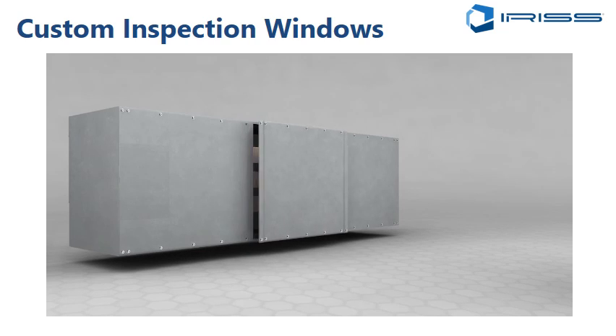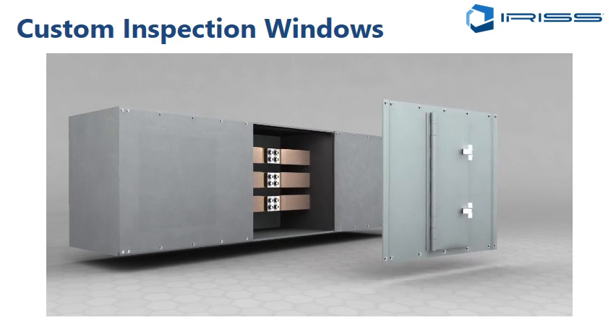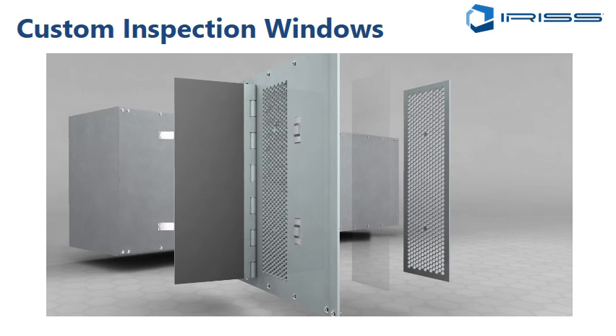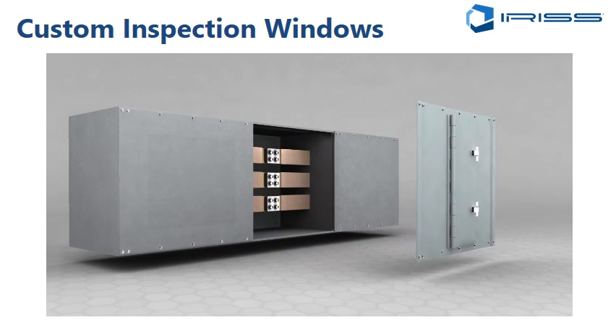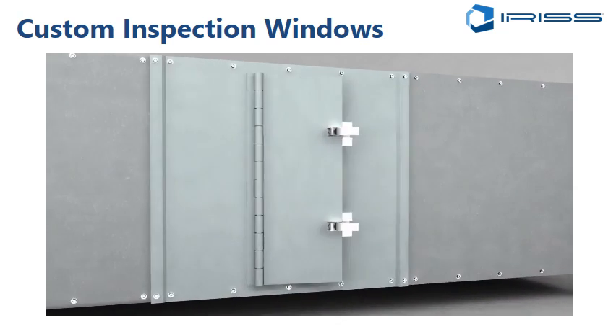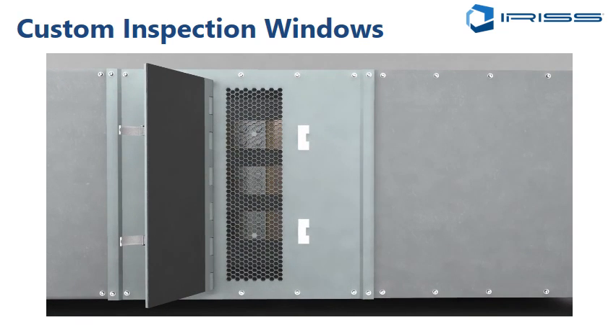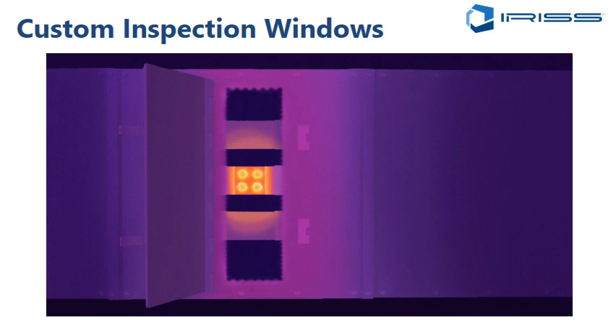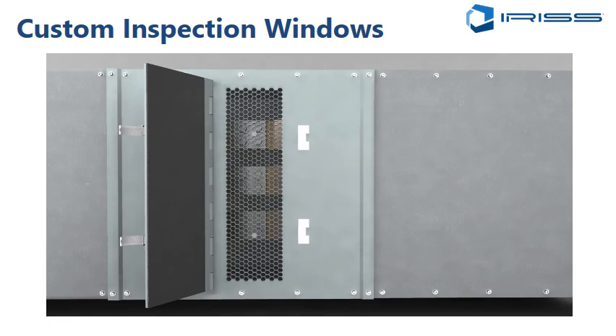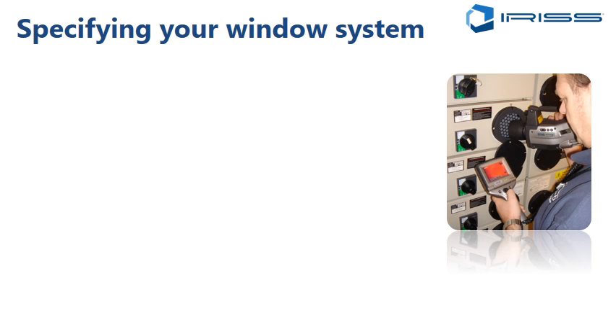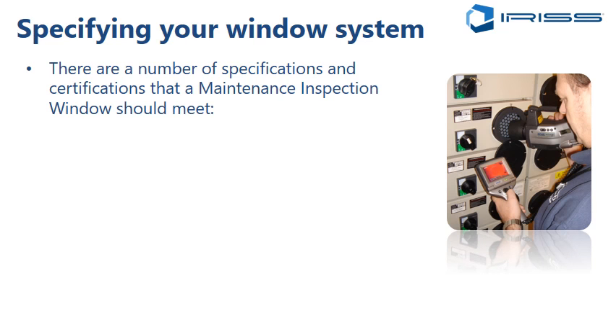When you look at this video here, what we do with a custom built solution, we take an existing cover and we actually make a maintenance inspection system that just bolts straight on in place of the old cover. Now these then enable me to see a visual, an infrared, a UV, take partial discharge and ultrasound measurements where applicable, and even have inbuilt temperature monitoring as well. So again, it becomes an inspection system, but in some cases it also becomes the access point for the de-energized maintenance as well.